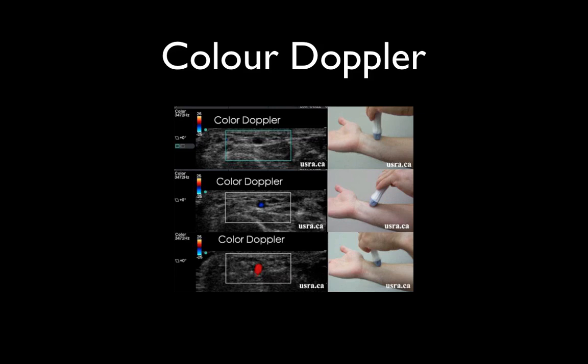Now, that's either because there's no flow in that vessel, which is one possibility, or it means that the probe is exactly 90 degrees to the flow of the blood or the object. So that signal is neither moving towards nor away from the receiver, from the probe, so you don't get a Doppler signal. So it's very important, if you're looking for a Doppler signal, to angle the probe slightly to and from the direction of flow of blood.